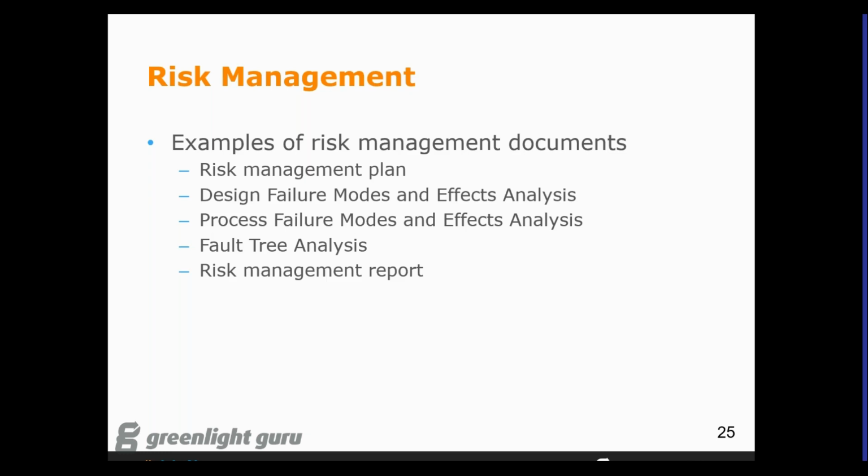Once it got documented, it got stuck in a file and didn't really get looked at again. Nowadays, with the latest version of 14971, the increasing focus on risk management within 13485, the risk files are starting to become more of a living document as originally intended.